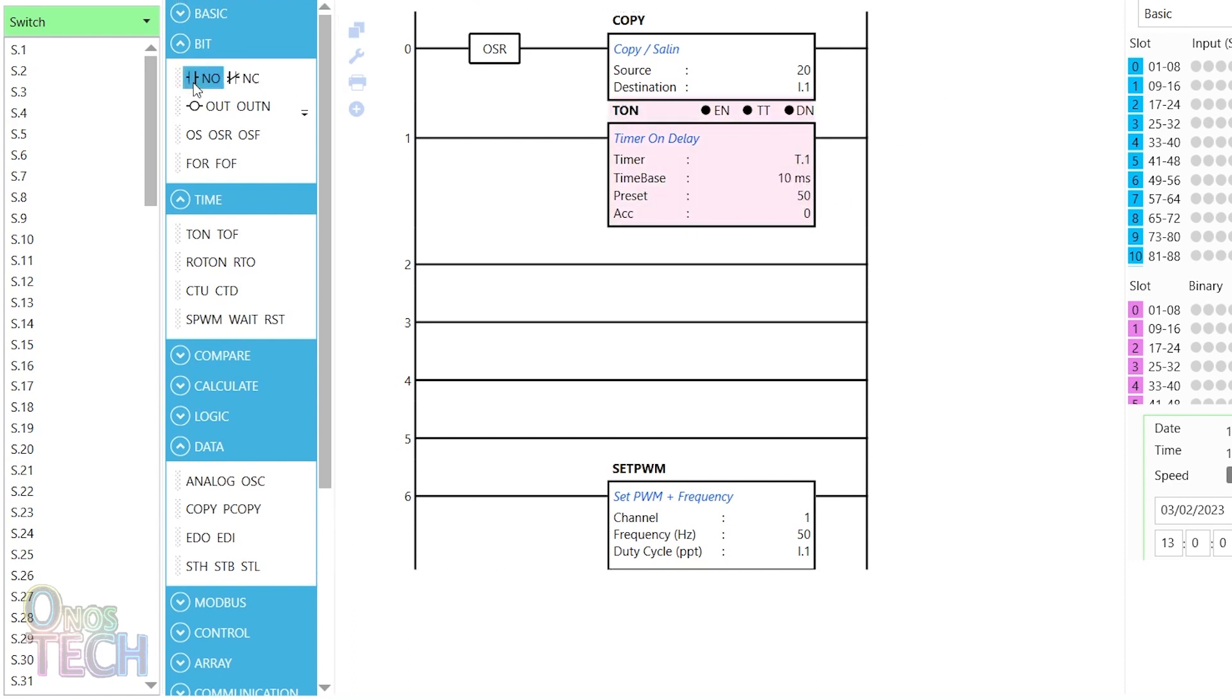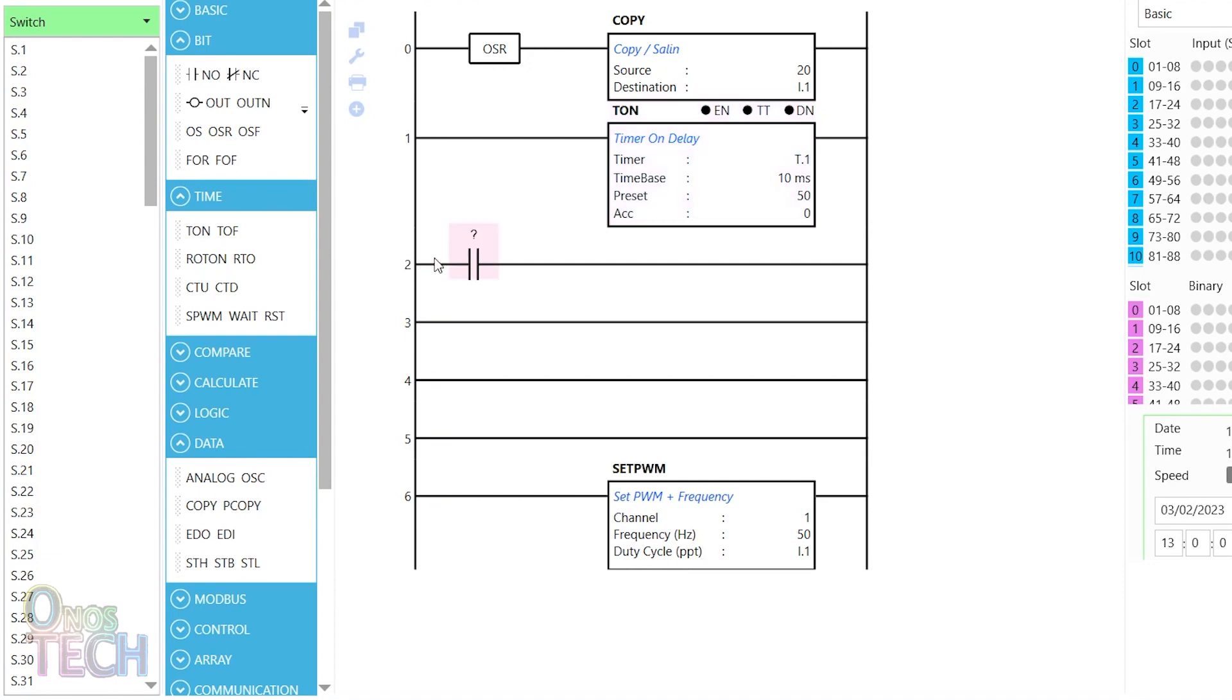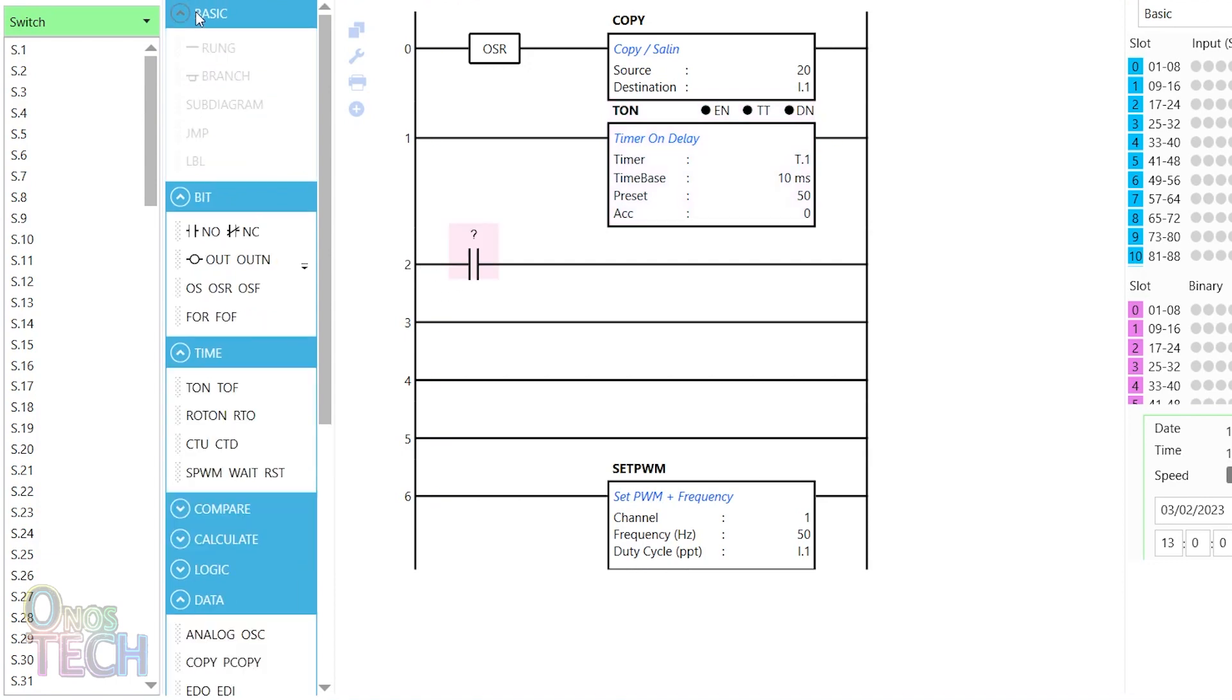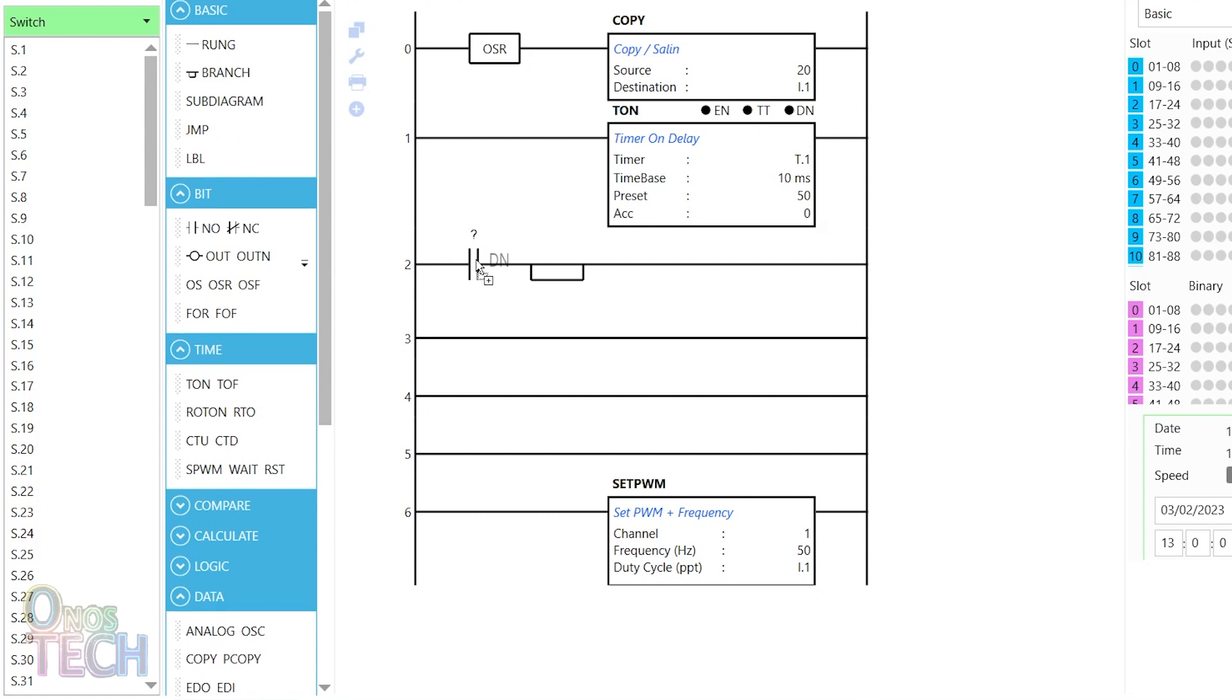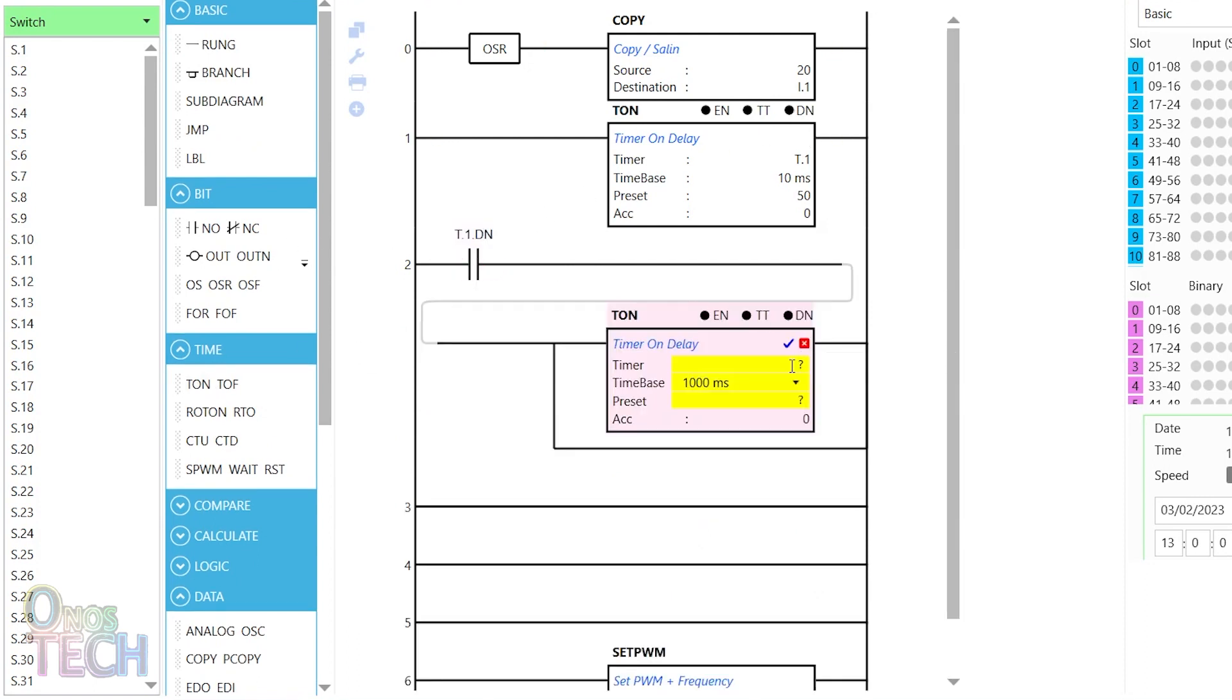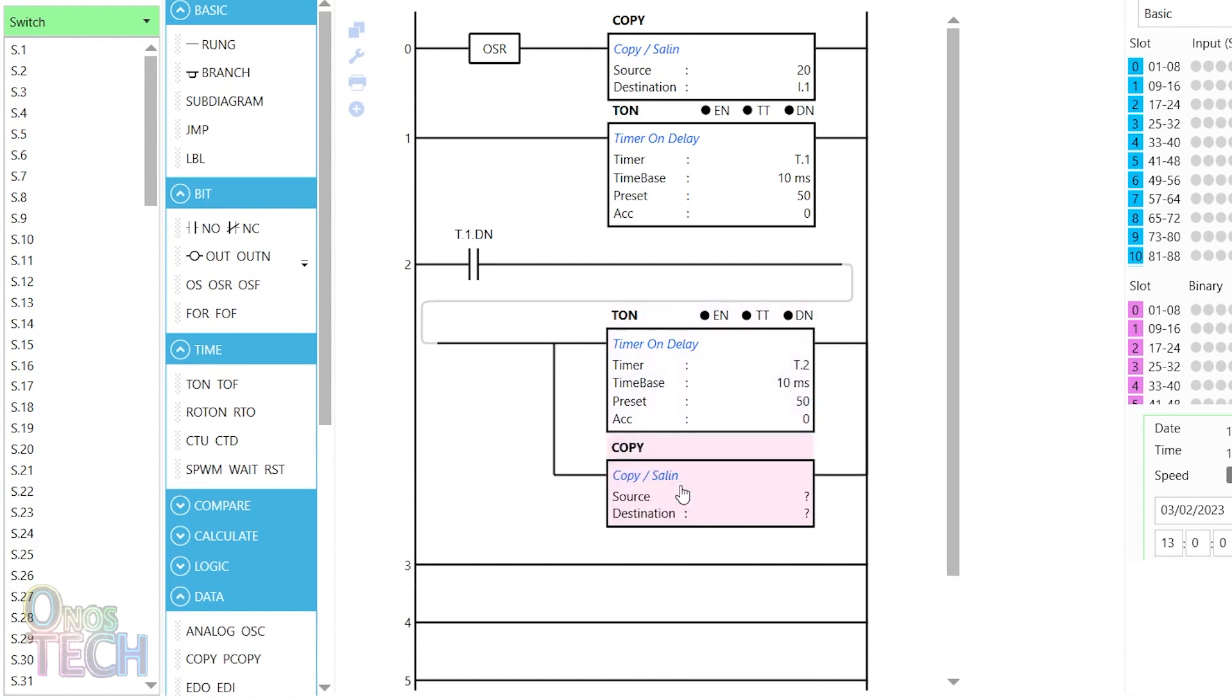Add a contact and a branch to the third rung. Drag the DN status of T1 to the contact, a timer on delay T2 to the first branch, and a copy instruction to the second branch. The copy instruction will position the motor at 0 degrees with 75 PPT.